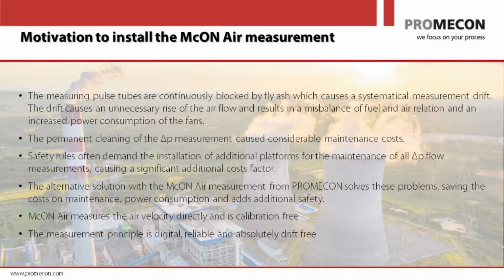What's the measurement range? I already mentioned that we could go down to 8 feet per second to start, or 6, 7 feet per second at the very low end. At the high end, there's actually no real limitation. Our velocity measurement is not tied to speed of sound or something. You know, we could even measure transonic speeds with this. But of course, for power station applications, the typical would be 100 feet, 120 feet per second, or 150 feet per second, whatever is desired. But those velocities are absolutely common for us, and we can cover them.